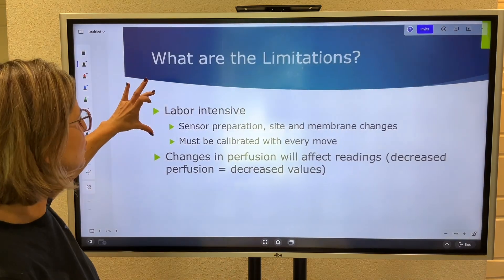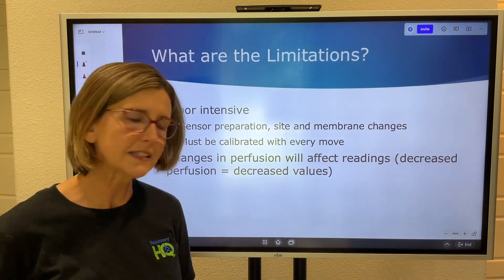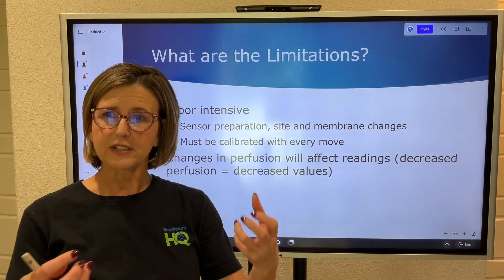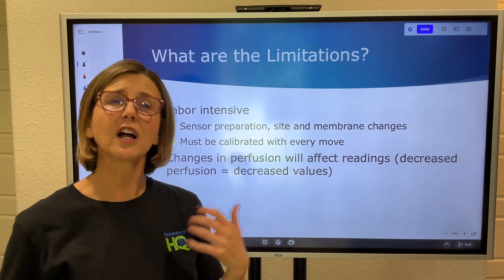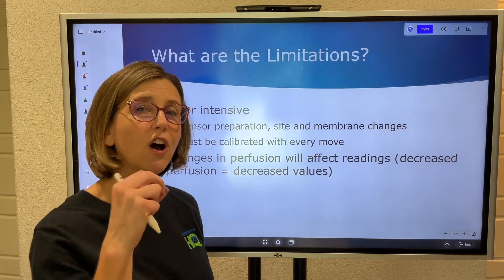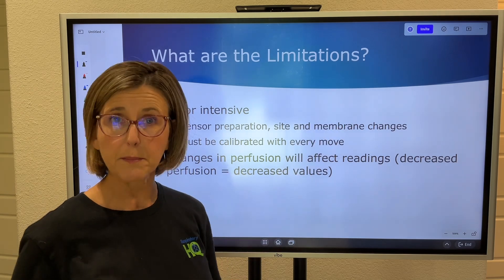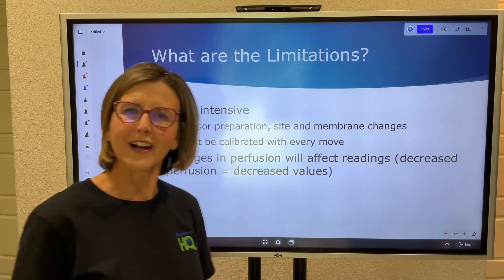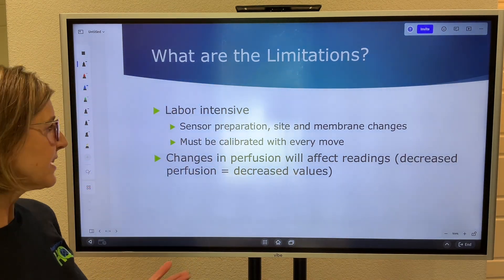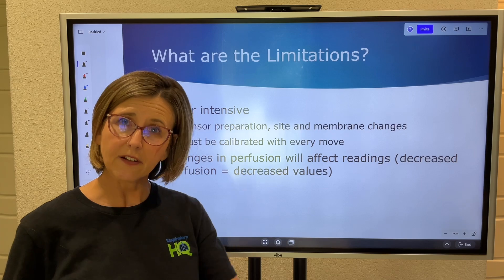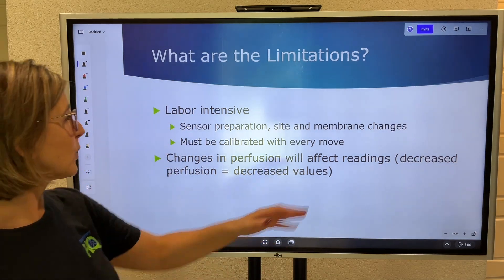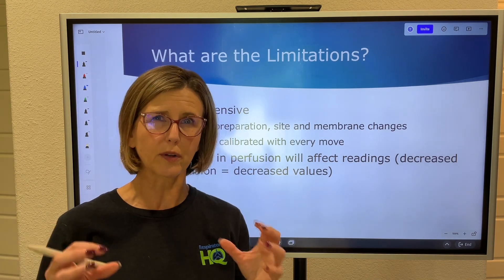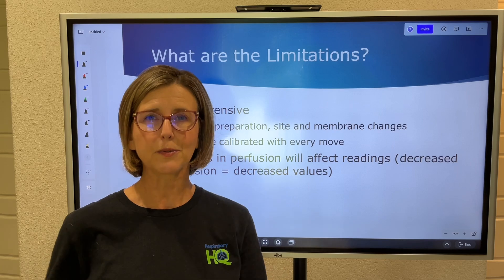There are limitations to know. It's labor intensive — you have to prepare the sensor, prepare the site, perform site changes and membrane changes. If it doesn't come into calibration, often something is wrong with the membrane. You must calibrate with every move. Also, changes in perfusion of that tissue will affect the reading — decreased perfusion produces lower values. It only works well when the infant is hemodynamically stable.